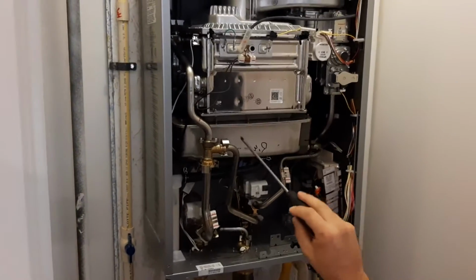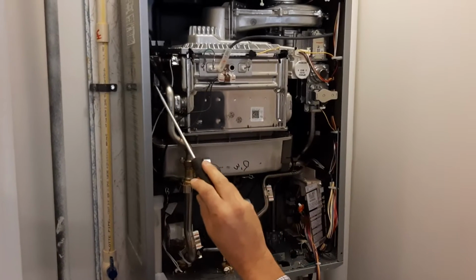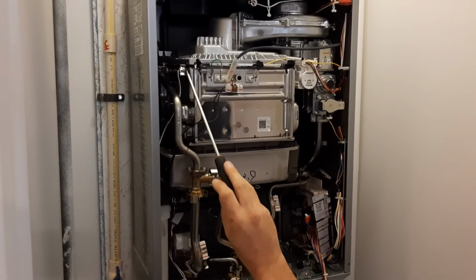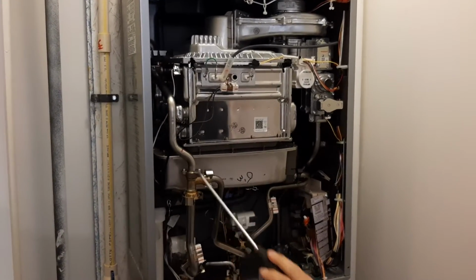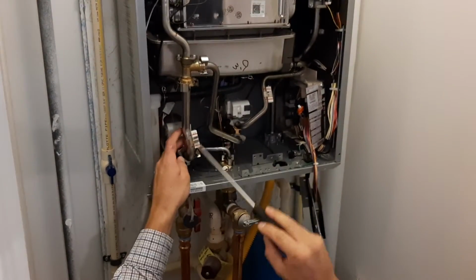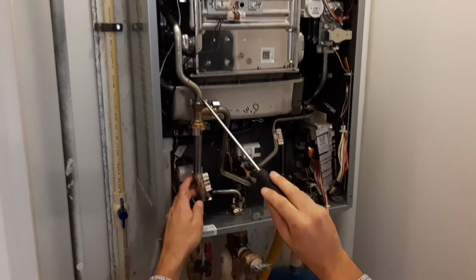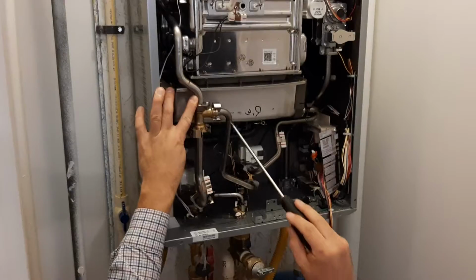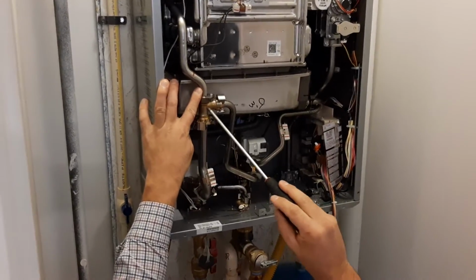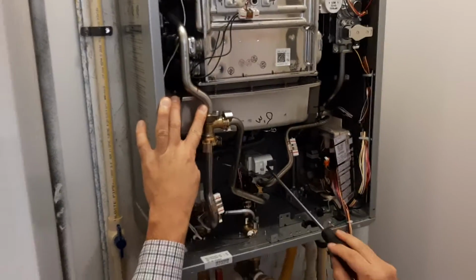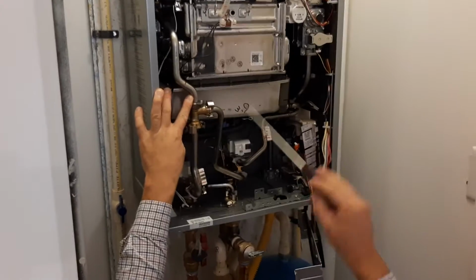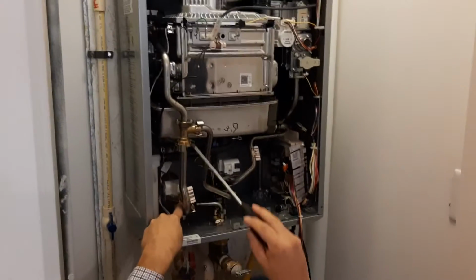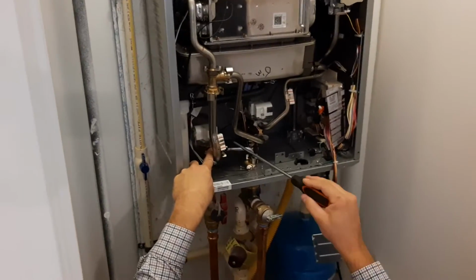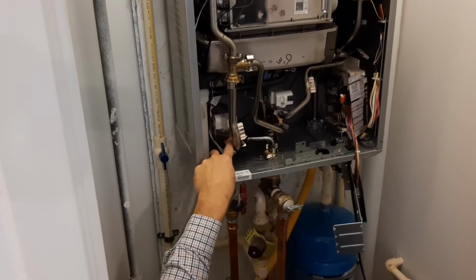Okay. So we're going to have water going through the unit, it's getting heated up, it's coming out of our heat exchanger. We know how hot it is coming out of the heat exchanger, and it's coming down. So at this point, if we know we're coming out of the heat exchanger too hot, we mix more cold water in to mix it down. If we're coming out not hot enough, then we would close this valve and force more water to be heated up. So then once we get here, that's how we control and get to 140 plus or minus a couple degrees. And this valve right here controls how much flow is going through the unit.